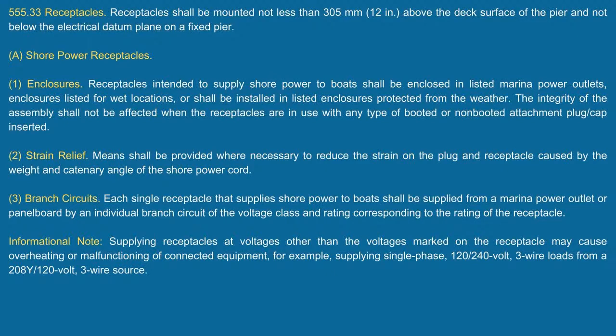When you look at these window units—somebody mentioned it, one of the J-Dubs at the jobsite, really appreciate it, shout out to you, brother—he mentioned why does a window unit have to have an individual branch circuit? The whole thing is, it's only drawing like 5 amps. Why can't it... it's not like it could be continuous, but the thing is if you have that set on a thermostatic control, there's no guarantee that AC unit's going to run for 3 hours or more.